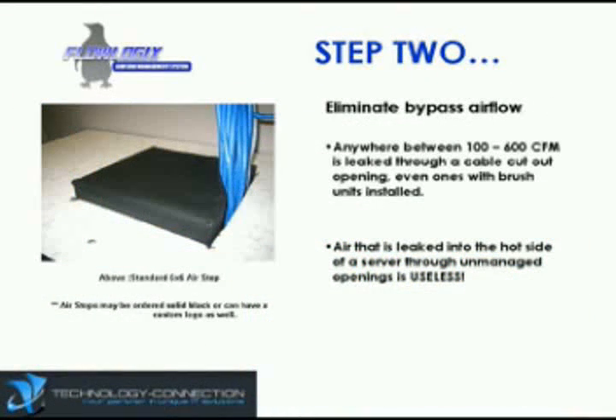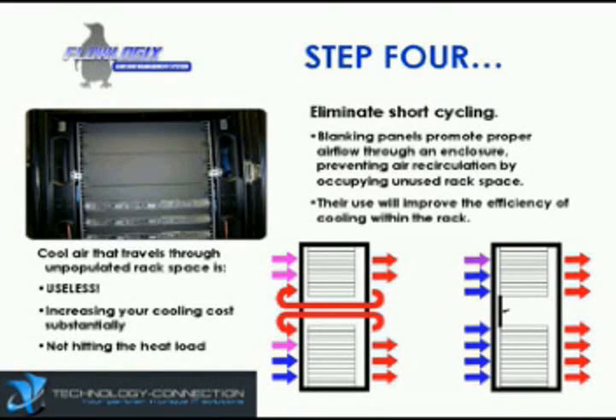Step two is installing our uniquely designed air stops to seal any unmanaged openings in the raised floor. Step three is strategically placing our air balancers within the subfloor according to our intellectual properties and proprietary software to balance out subfloor velocity and pressure. Step four is the finishing touch — by adding blanking panels, short cycling air is eliminated.